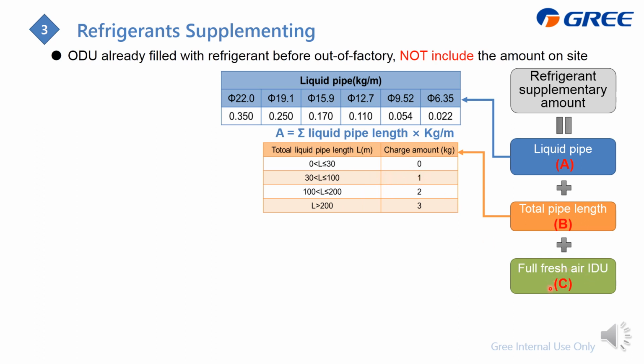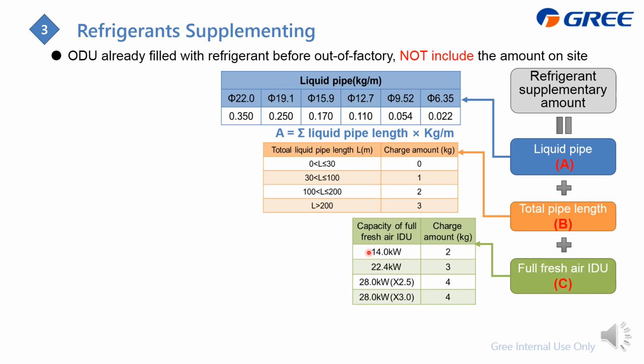And the C part is if the indoor units include the fresh air indoor unit. According to the indoor unit capacity, you also need to charge an additional amount. After that you can get the refrigerant supplement amount. Then next is to charge it, right?